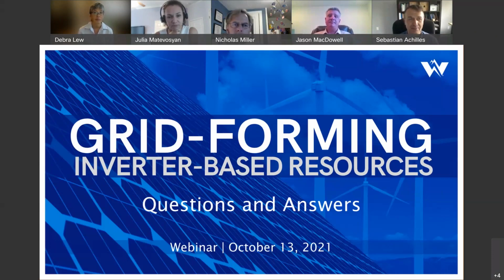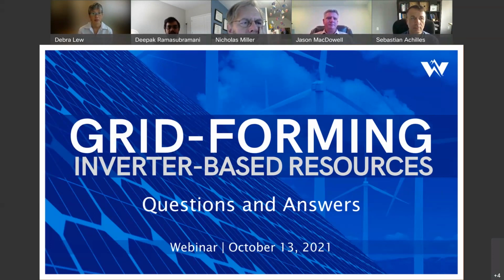It's not clear yet. I think it also affects time to deploy. If you want one device to provide every service, the time to deploy that device or equipment increases, because it takes longer to design, develop, and ensure it's robust. For example, if we want every grid-forming device to also be black start capable, that will take much longer to ensure every grid-forming inverter has the necessary resources for black start. But if the goal is to stabilize the region of the network 85% or 90% of the time over a 10-year operation, so you can extend the number of inverter-based resources or keep it more stable, then that resource doesn't necessarily need to be grid forming with black start capability—it can be grid forming in a different manner, just to improve the stability of that region.